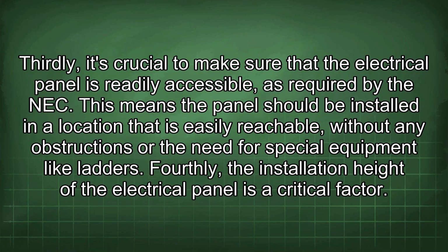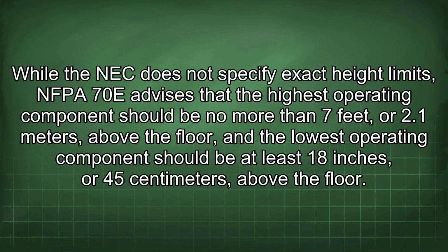Thirdly, it's crucial to make sure that the electrical panel is readily accessible as required by the NEC. This means the panel should be installed in a location that is easily reachable without any obstructions or the need for special equipment like ladders. Fourthly, the installation height of the electrical panel is a critical factor. While the NEC does not specify exact height limits, NFPA 70E advises that the highest operating component should be no more than 7 feet or 2.1 meters above the floor, and the lowest operating component should be at least 18 inches or 45 centimeters above the floor.